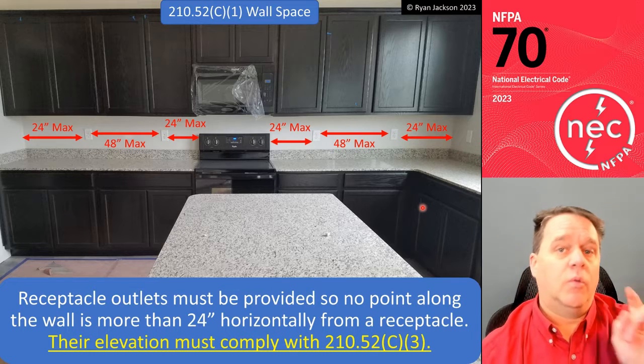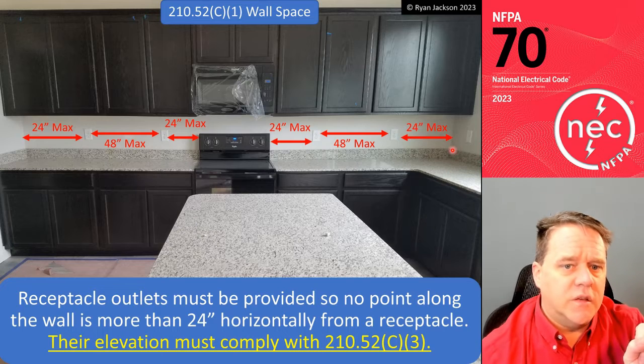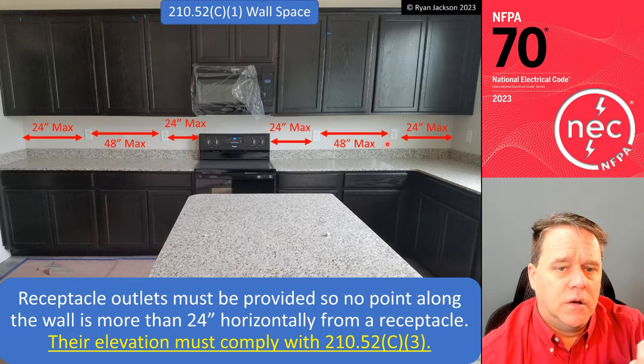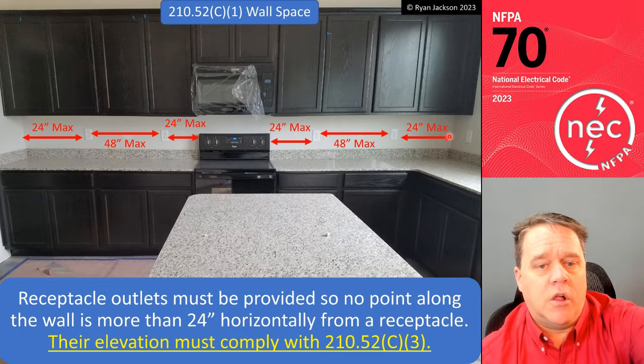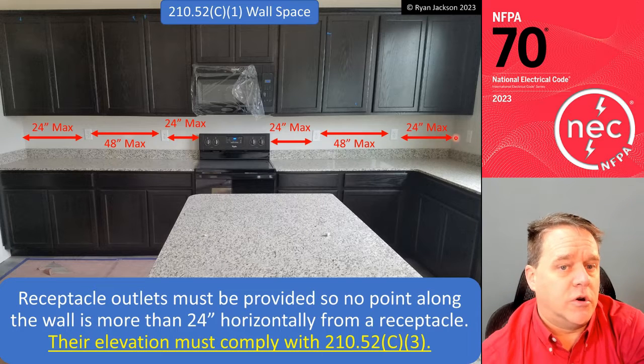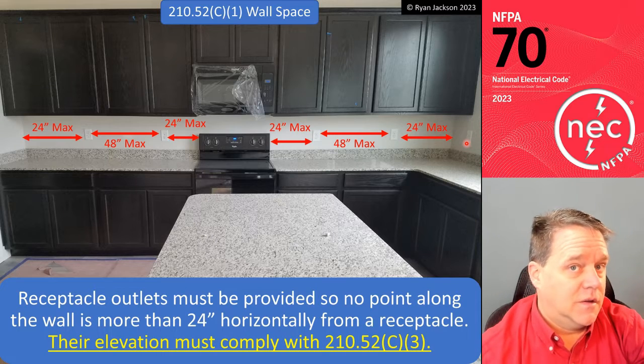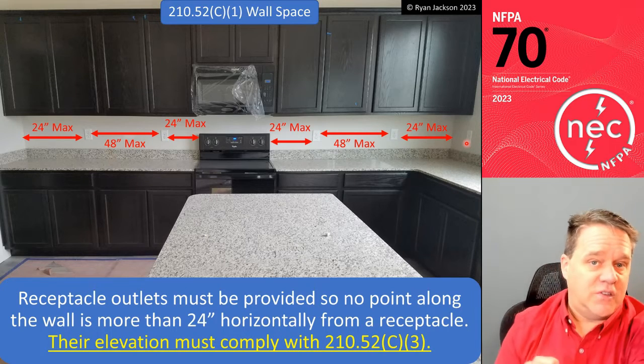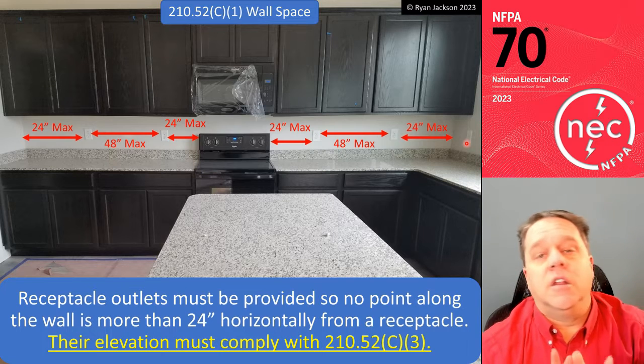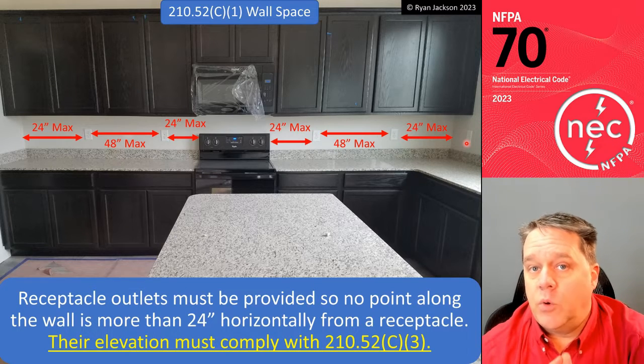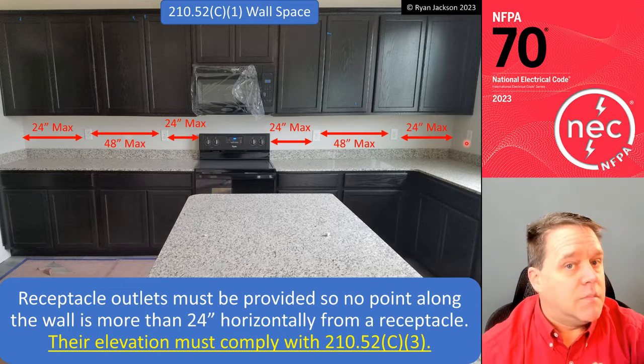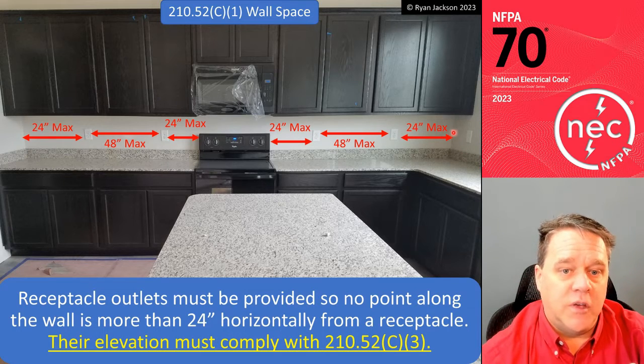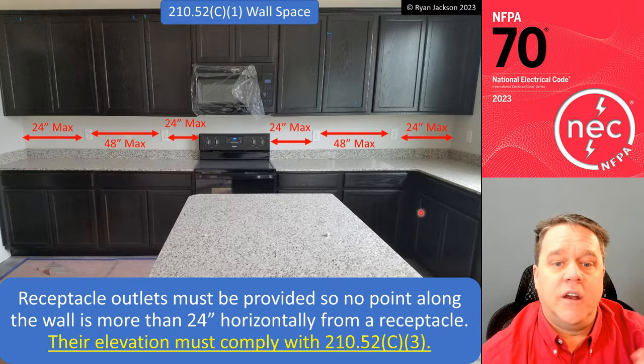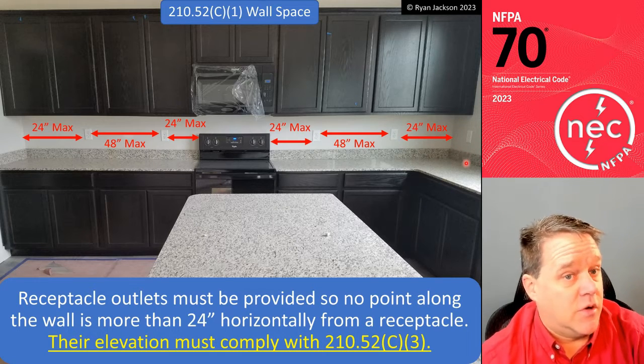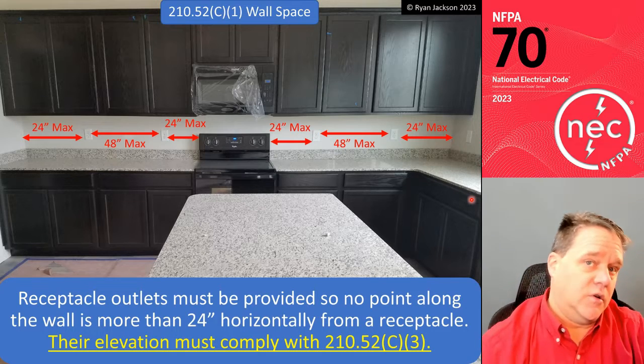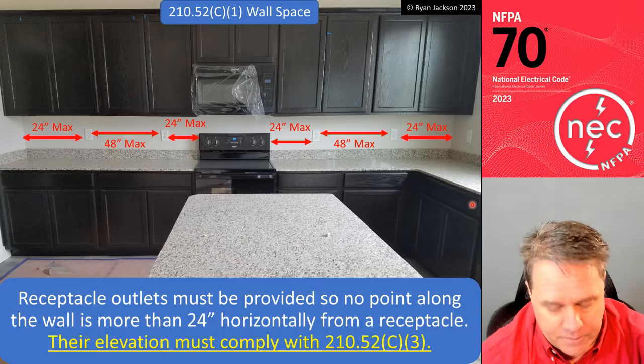All right? So where I'm going with this is, what if I had a receptacle here, and then it was 3 feet to the wall, and then I continued the measurement around the corner and added a receptacle within 1 foot? Would that satisfy the 4-foot spacing thing? Well, yes, but you need to be able to touch a receptacle outlet within 2 feet of any point on the wall space. And I think most people are going to say that the wall space measurement starts here and then it restarts at that corner for the purposes of countertop. Again, the code's not clear on that, so ask your inspector and results may vary.